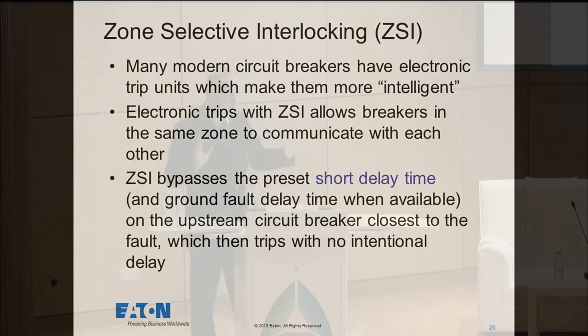What happens is the breakers in the same zone of protection communicate with one another. I'm going to give you a little cartoon to demonstrate what I mean. Ordinarily, this breaker up here, set to a 1/2 second delay, will sit there and wait if a fault occurs downstream, because the delay was intentionally set to provide a coordinated system for the facility. This allows it to bypass some of the settings and go faster to limit the amount of energy. We use the acronym ZSI, Zone Selective Interlocking. It was originally developed just to help with coordination, but now we recognize that it's very helpful for arc flash.